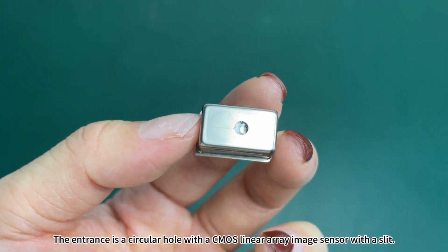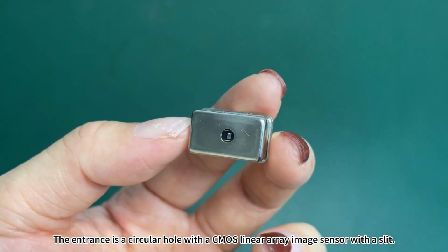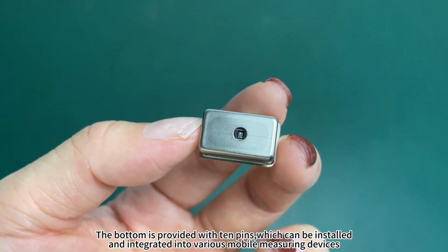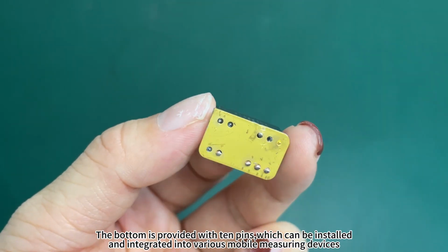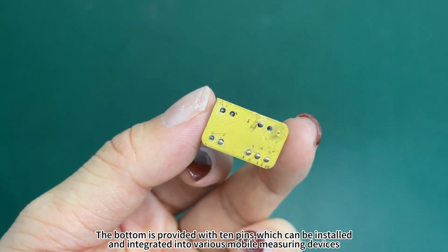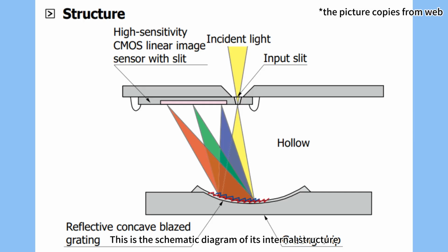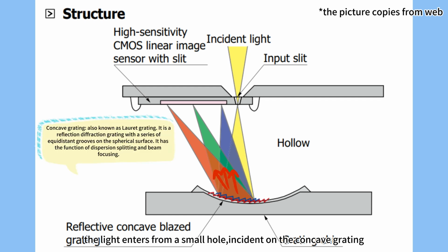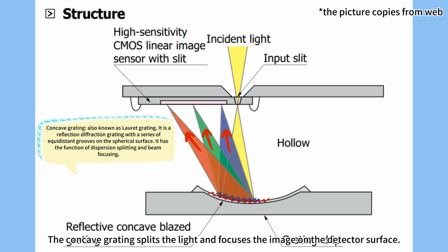The entrance is a circular hole with a CMOS linear array image sensor with a slit. The bottom is provided with 10 pins, which can be installed and integrated into various mobile measuring devices. This is the schematic diagram of its internal structure. The light enters from a small hole, incident on the concave grating. The concave grating splits the light and focuses the image on the detector surface.